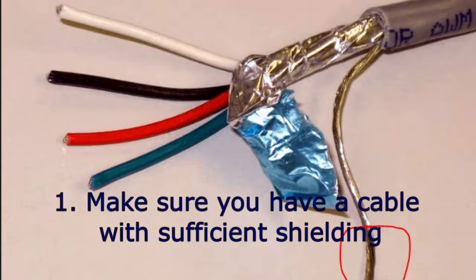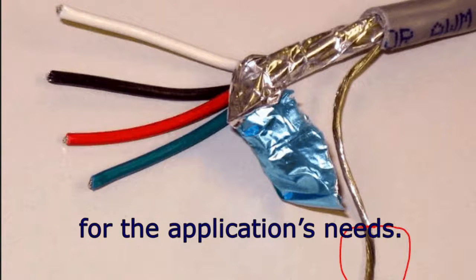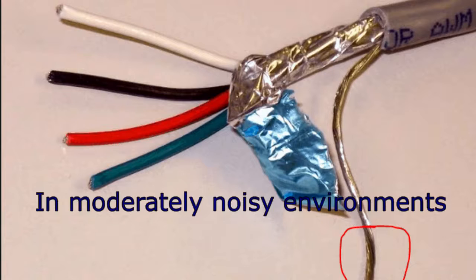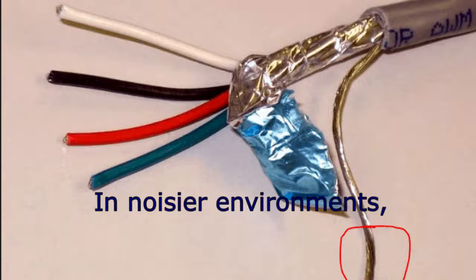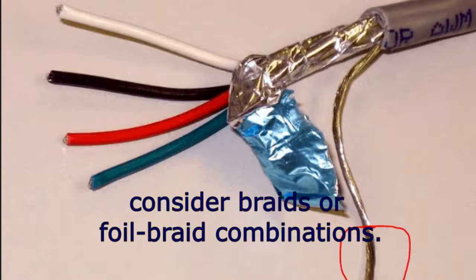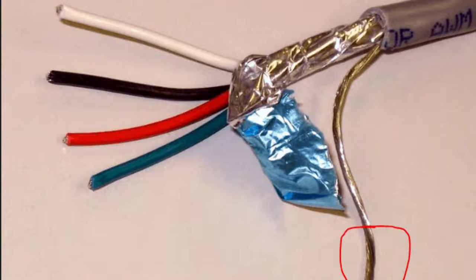Practical guidelines for effective shielding: One, make sure you have a cable with sufficient shielding for the application's needs. In moderately noisy environments, a foil alone may provide adequate protection. In noisier environments, consider braids or foil-braid combinations.